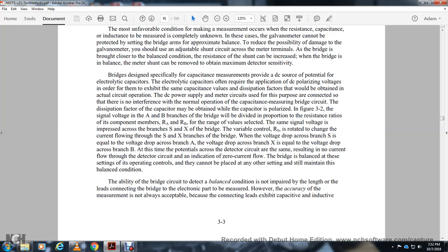The capacitor is polarized with the same voltage as in Figure 3-2. Signal voltage is divided proportionally by the ratio of resistors A and B. The same signal voltage appears within branches S and X of the bridge. When the voltage drop across branch S equals the voltage drop across branch A, and the voltage drop across branch X equals the voltage drop across branch B, no current flows through the detector circuit — indicating the bridge is balanced.